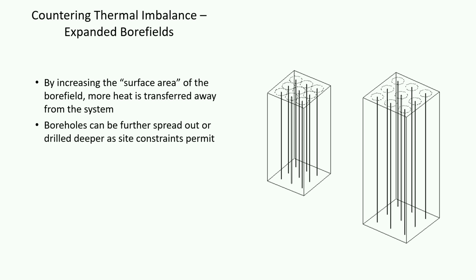First and foremost, we can take care of this through changing the geometry of our bore fields. If you're able to spread out your boreholes or drill them deeper, you're essentially increasing the surface area that you have to let heat escape from that system. Now, a lot of times in New York, particularly in these small footprint, high-rise buildings, we're pretty limited in what we can do in this regard. Being able to drill deeper than 500 feet helps, but in general, we're constrained on a small site. We do this as much as we possibly can, and then may have to use other alternatives.